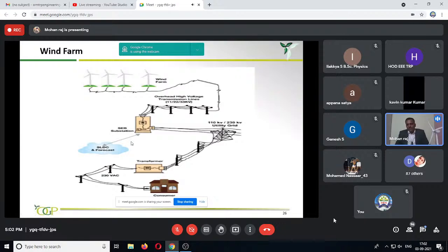So what is called a wind farm? A group of wind turbines is called a wind farm. In a wind farm, multiple wind turbines are connected to the state electricity board substation. For example, in this single line diagram, 4 wind turbines are connected to maybe 11 kV, 33 kV or 66 kV lines, and it is further connected to the state electricity board substation or a private electricity substation, which can further convert to a higher level, from 11 kV to 33 kV.